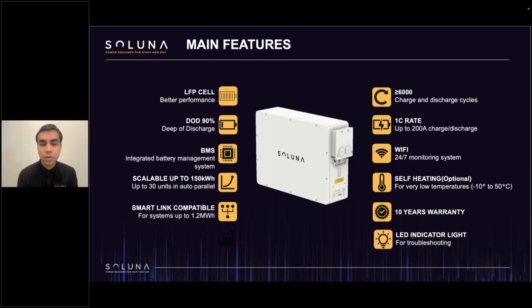In this case, for Canada, the best way to install it will be within a home where there is heat already, because the low temperature will be considered -10 Celsius. Then you will have an alarm, and the BMS will tell the battery to go to sleep. In this case, tech support will help you get it back on, but the main thing is to keep it in a warm place. SmartLink compatible for systems up to 1.2 megawatt hours, 10-year guarantee, and with LED indicator lights on the side.